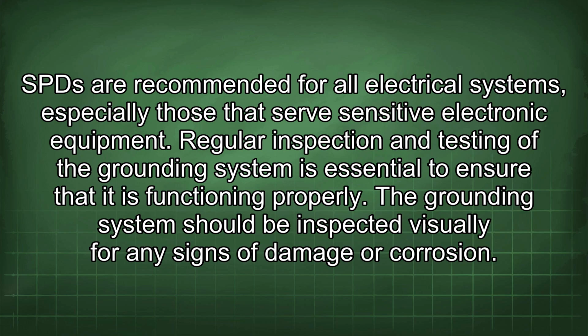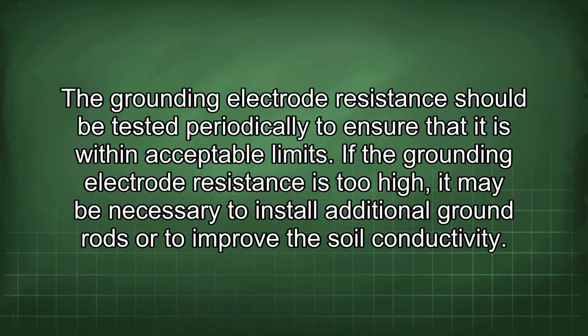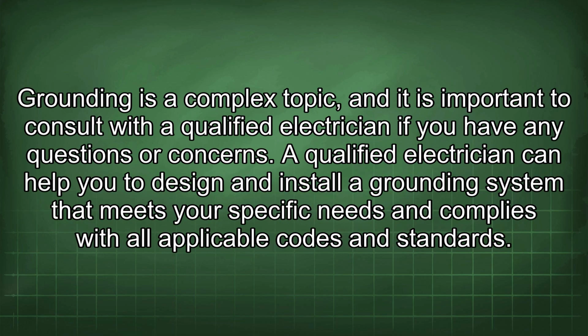Regular inspection and testing of the grounding system is essential to ensure that it is functioning properly. The grounding system should be inspected visually for any signs of damage or corrosion. The grounding electrode resistance should be tested periodically to ensure that it is within acceptable limits. If the grounding electrode resistance is too high, it may be necessary to install additional ground rods or to improve the soil conductivity.